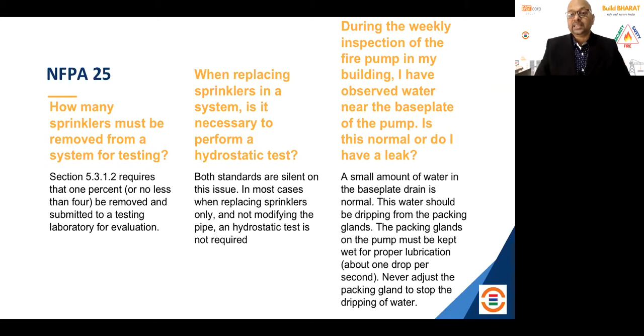You can see in the pump house, on the base plate, there is always the gland packing which is always leaking. So the question might come for many people: this pump is giving leakages because it is always dropping water from the gland packing, is it allowed? Yes, it is the best practice. One drop per second is acceptable. Never adjust the packing, because it is healthy practice to have some leaking, but it should not be a complete continuous pour out of the pump. So this is all about your visual inspection, which will be part of your operation and maintenance practices.